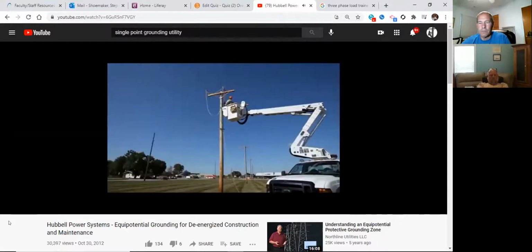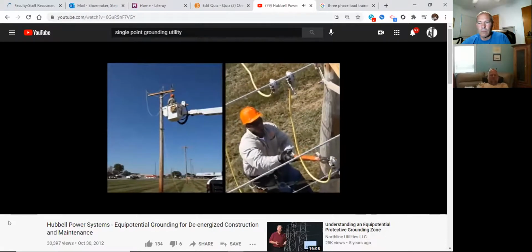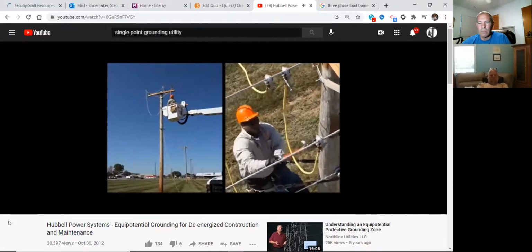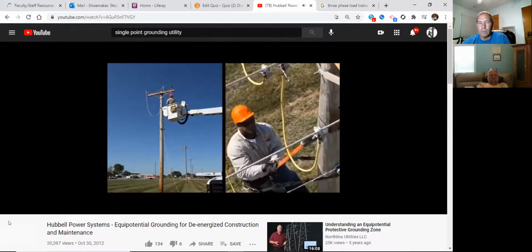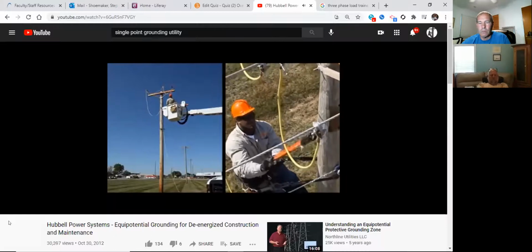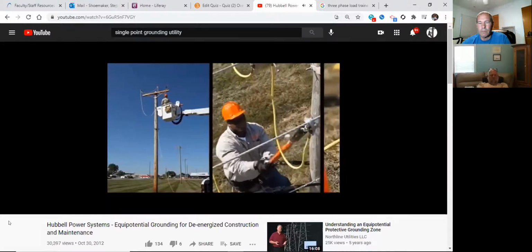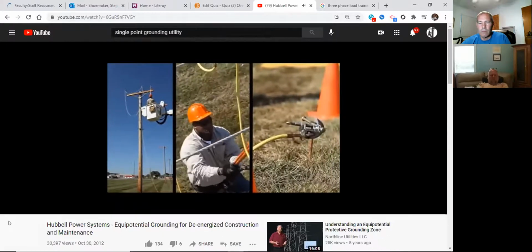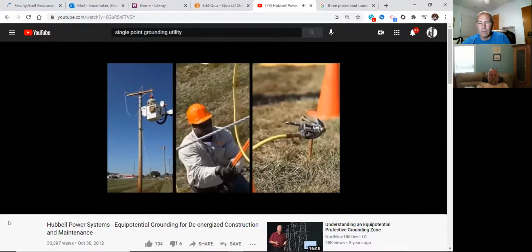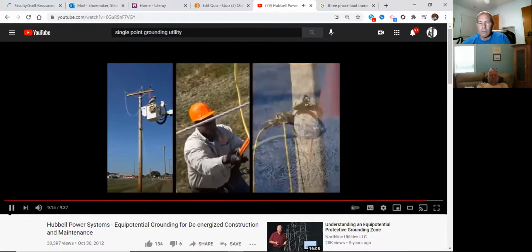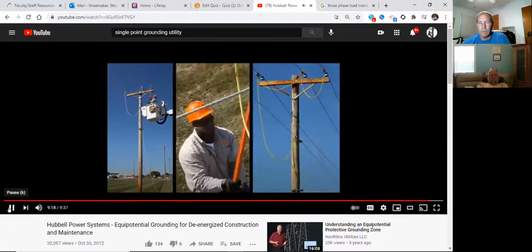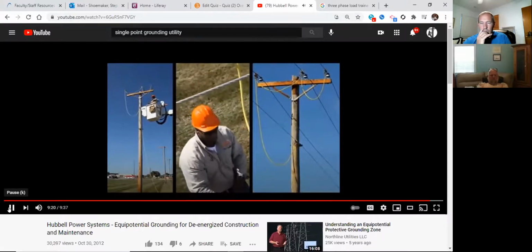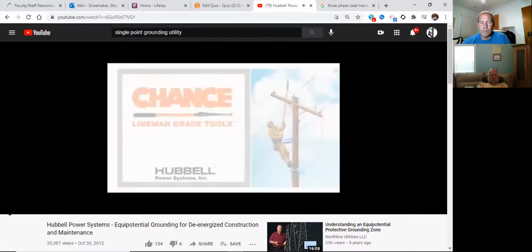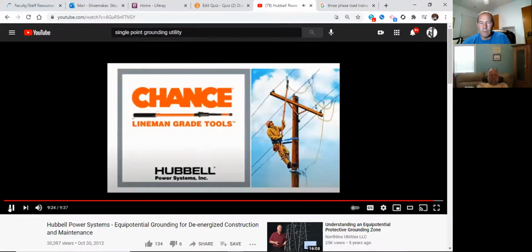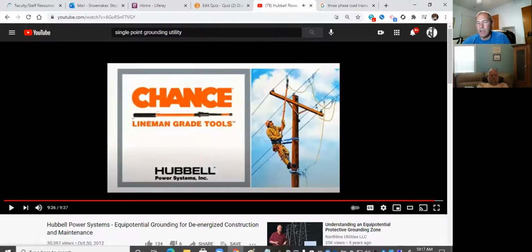Of course, the very same methods can be applied just as well from an insulated bucket truck. Whether the work is done from the pole or out of an insulated bucket truck, the same dual point or single point method must be used to provide an equal potential zone of protection for the lineman. Whatever your work practices, either the dual point or the single point method establishes an effective personal protective zone for de-energized construction or maintenance work, an equal potential zone with proper temporary grounding. Be sure you are in the equal potential zone. Okay, that pretty much wraps it up as far as the installation of them.